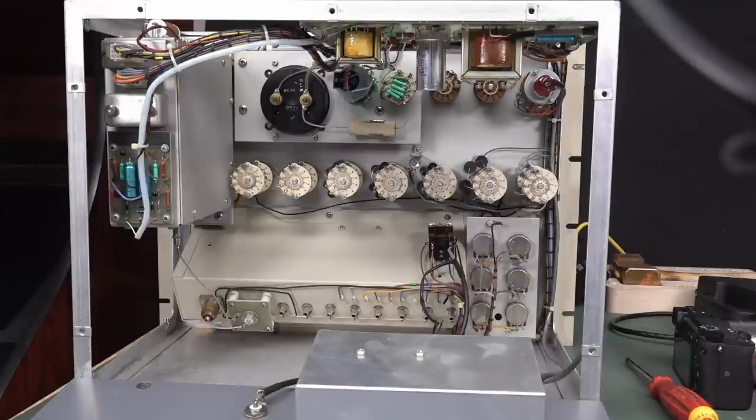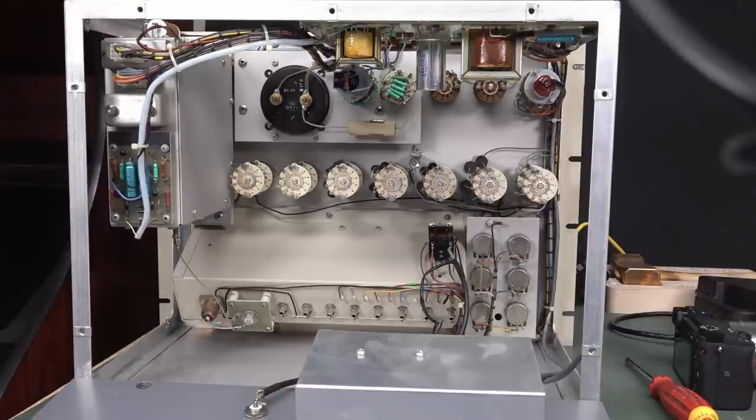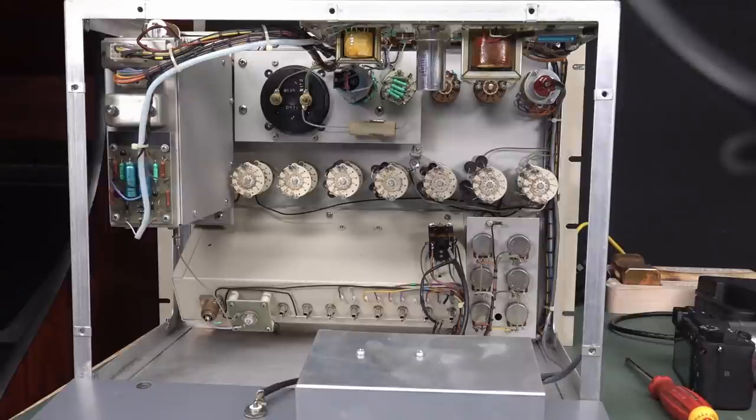So they certainly didn't need to make it that big. But it was made for a particular market. As I said, this is not designed to be like a desktop instrument or anything like that. But there's really a lot of art that's gone into this. Especially in terms of, like, we could really spend hours looking at how all the guarding system works and stuff like that. And just the layout of the wiring and the shielding and the guarding to prevent leakage. And all sorts of other stuff interfering with incredibly low current measurements.